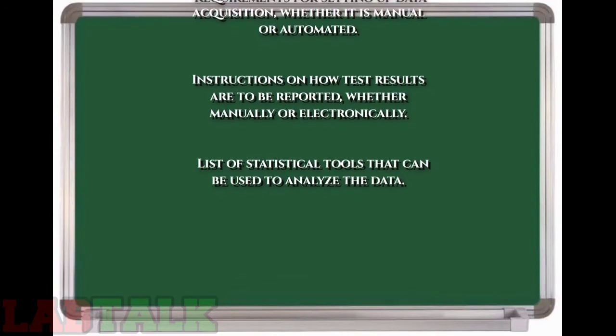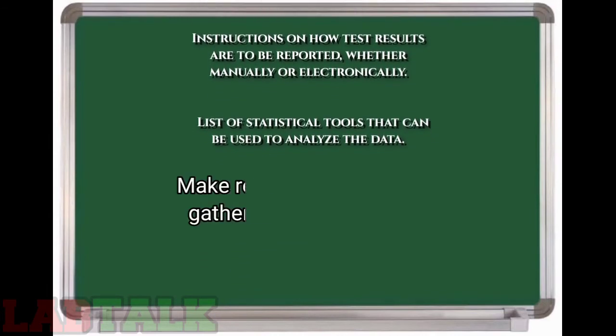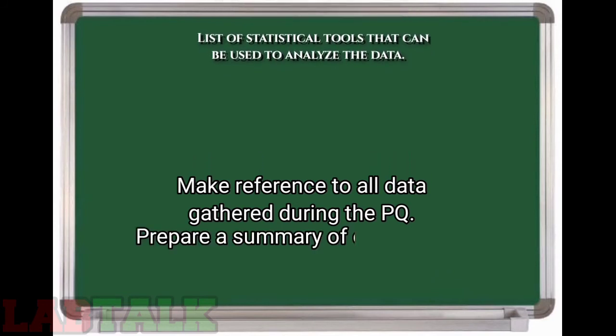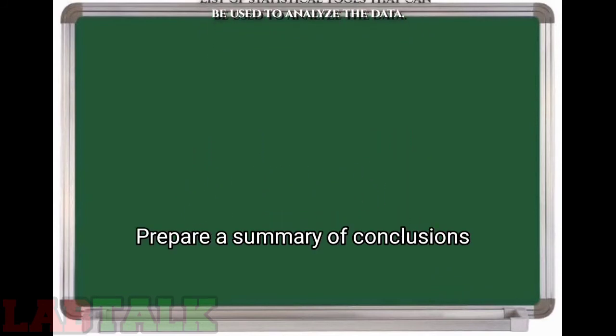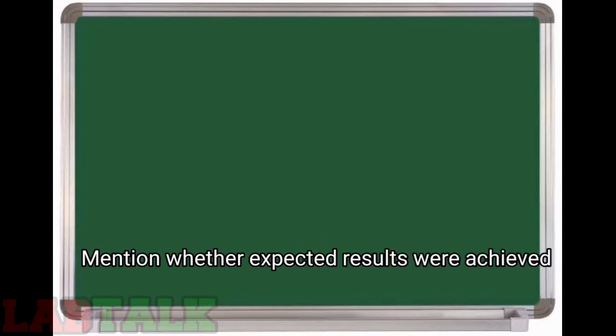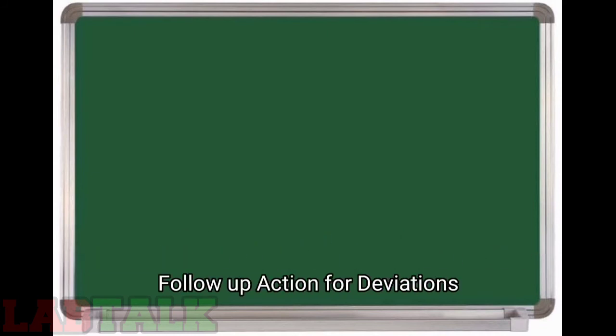Instructions on how test results are to be reported, whether manually or electronically. List of statistical tools that can be used to analyze the data. Make reference to all data gathered during PQ. Prepare a summary of conclusions drawn. State whether the expected results are achieved and any follow-up activities are needed or not.